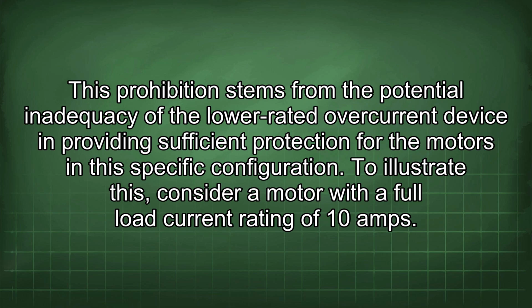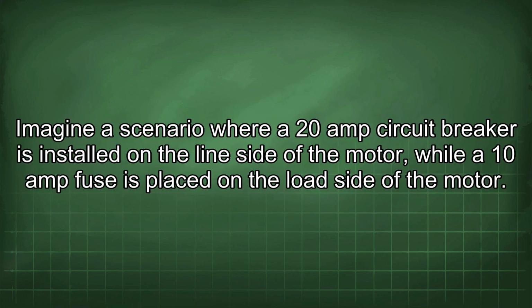To illustrate this, consider a motor with a full load current rating of 10 amps. Imagine a scenario where a 20-amp circuit breaker is installed on the line side of the motor, while a 10-amp fuse is placed on the load side of the motor.